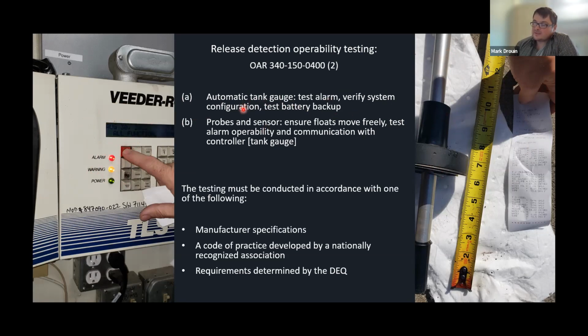And then you want to verify the system configuration. I call it the in-tank setup report. I don't know the official name, but that is basically how this tank gauge is programmed to communicate with this probe or sensor, or something that you have out there. So as an example, let's say you have a facility with 3 underground storage tanks. We want to see maybe 3 probes in those tanks, and we want those programmed correctly. We want to make sure that the diesel probe is programmed correctly, the unleaded probe is programmed correctly, and all the other parameters with that. So that's what we're looking for you to look at.